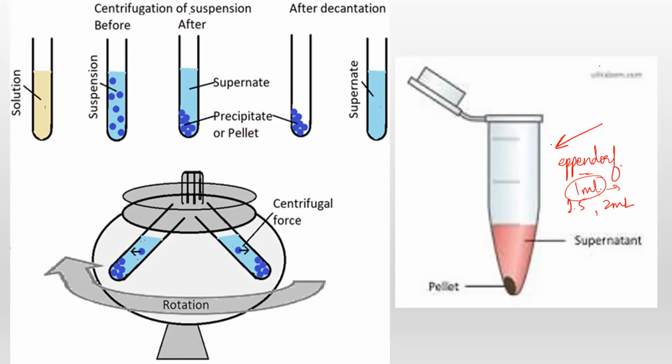So based upon what volume you are working, you can decide whether you want to use a centrifuge or an Eppendorf for smaller amounts. And so this can fit in a microfuge. The microfuge also has the same principle. There is a rotor in the microfuge. You also have to balance the microfuge. There will be a lot of holders in the microfuge. Actually, a microfuge comes with about 12 or even more holders. So you will have to counterbalance.